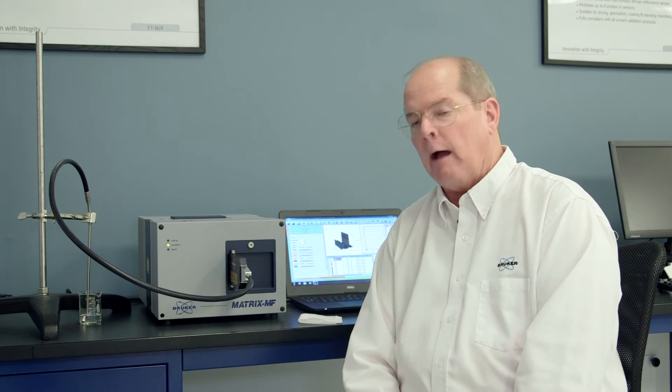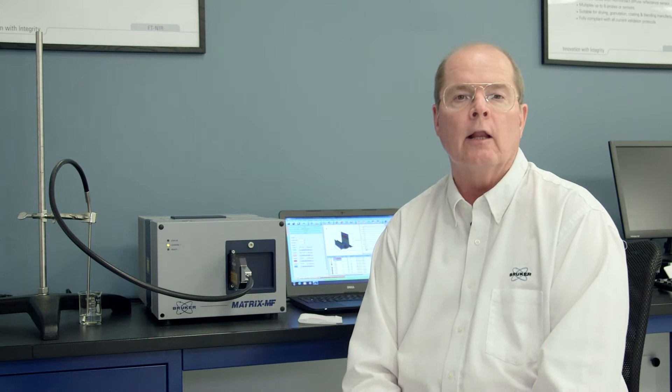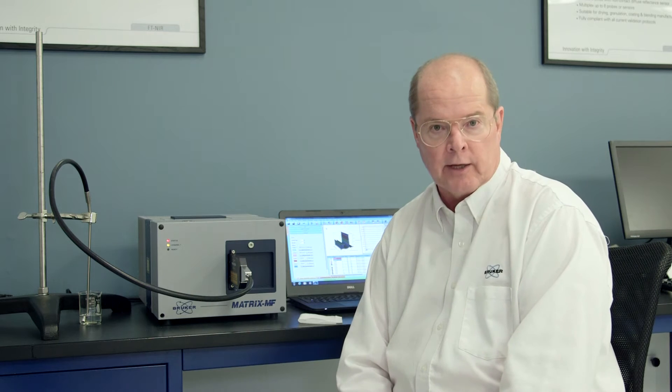The fiber-optic probe is a silver halide fiber with a spectral range from 4,000 down to the cutoff of the detector, which in this case is about 650 wave numbers.